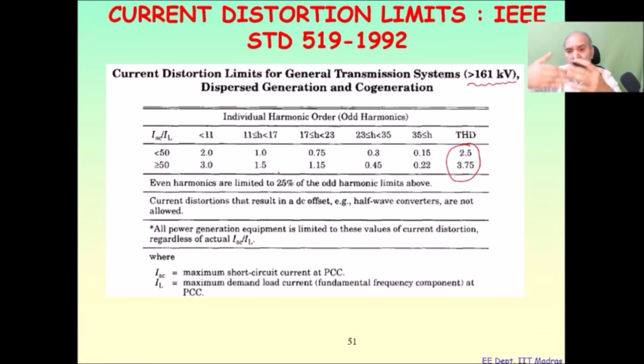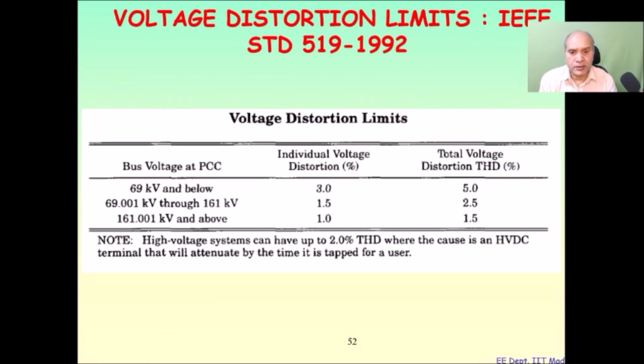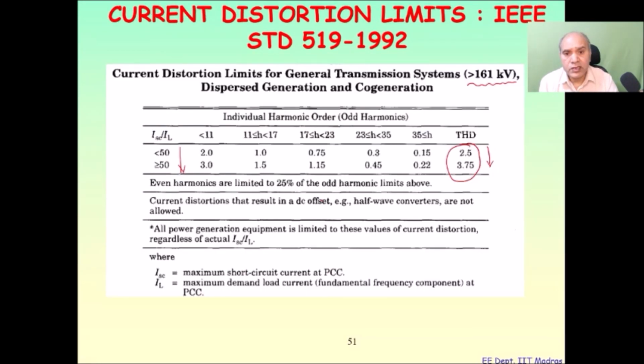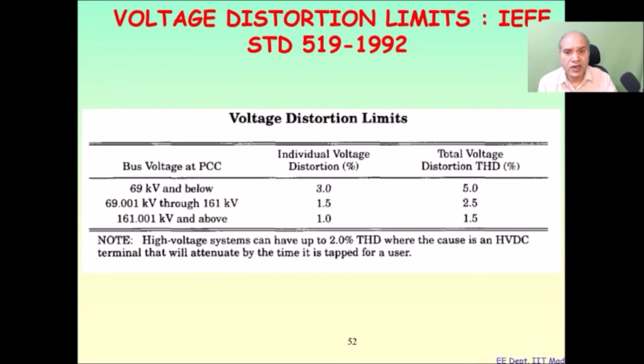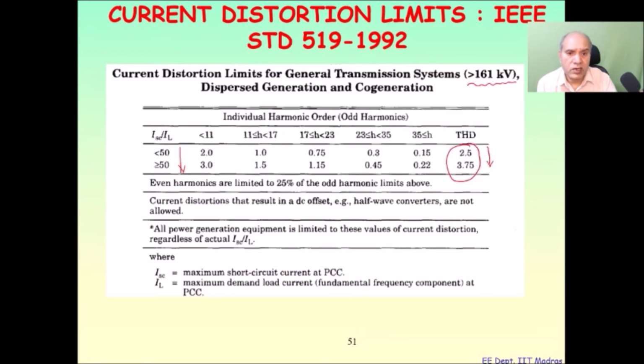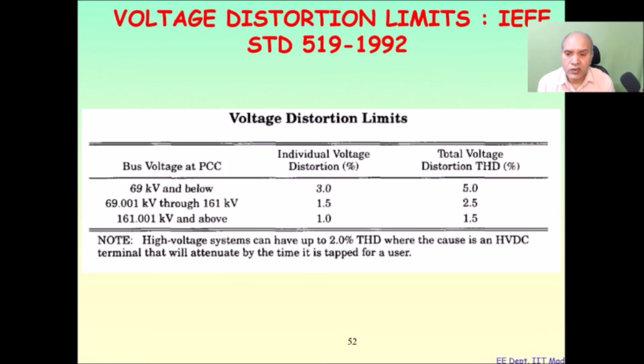But in a nutshell, they indicate the same kind of behavior. So you see that when the voltage goes up and up, the permitted values of harmonics are less and less. And for an increasing value of short circuit ratio of the bus, the allowable TDD can be slightly more than for those having less SCR. I hope you understand this pattern. So this was about the current aspect, and if you go for voltage distortion, for the voltage one, if 69 kilovolt and below, the allowable THD is 5%, for 69 to 161 it is 2.5, and above 161 it is 1.5.